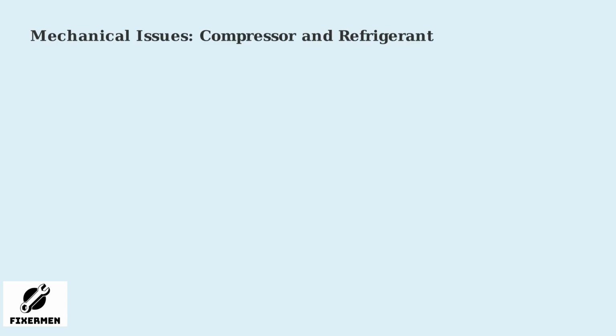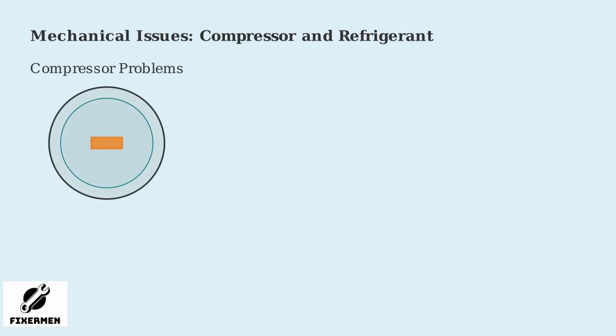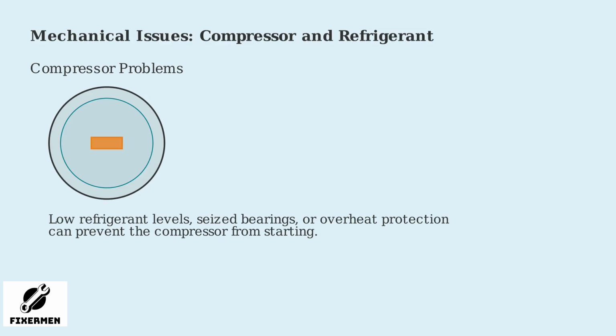If the electrical components check out fine, the problem may lie in the mechanical parts of your Trane XR15 unit. Let's examine the compressor and refrigerant system, which are critical for the unit's operation. The compressor is the heart of your XR15 unit. Common issues include low refrigerant levels that reduce pressure, seized bearings that lock up the internal mechanisms, or overheat protection that shuts down the unit to prevent damage.